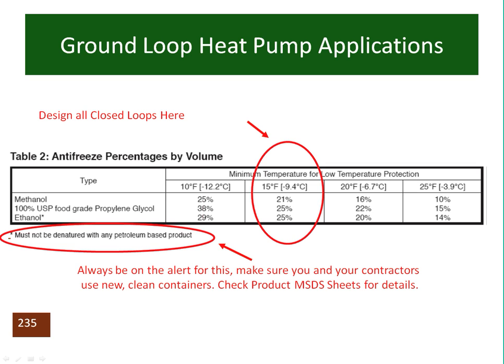I don't personally care for propylene glycol because it is difficult to get enough fluid flow out in your ground loop to make sure that you have proper turbulence, so you have good capacity or full capacity out of your ground loop. Typically, in most systems, you're going to have to pump at least 4 gallons a minute through a glycol loop field to have a prayer of sneaking up on turbulent fluid flow, or a Reynolds number of 2,500.